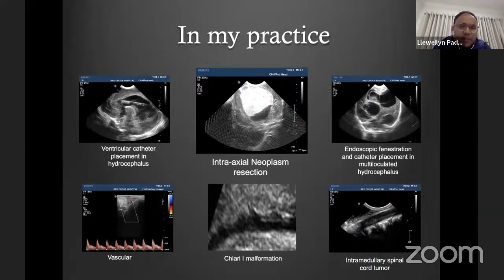but generally the craniotomy itself may need to be extended slightly to allow for the probe, but with the modern probes, the high frequency probes tend to have smaller footprints, so you can use them within your standard craniotomy. And I found increasingly that I don't need to increase the size of my craniotomy to image. Sterility, again, these follow protocols intraoperatively, but it's very important that the probe be sterilized correctly. Some of the probes in the market can be sterilized together with the rest of your instruments. Others need to be placed through a sterile sheath. The image quality, spatial resolution, the probe frequency, and probe size is something you need to become quite familiar with.